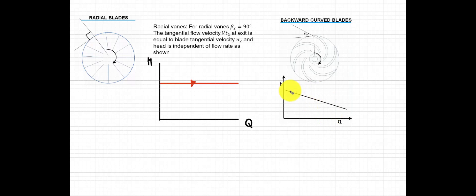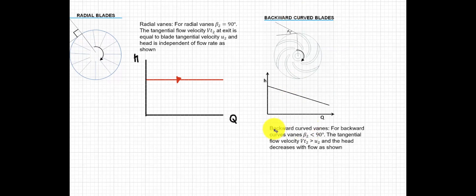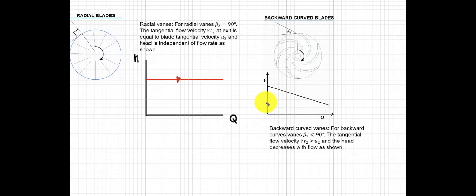It still depends on the manufacturing. Usually, you operate at the required head in the system and the corresponding volume flow rate — if you can push the fluid at that amount and that pressure required by the system. For backward curved vanes, the angle is less than 90 degrees. The tangential velocity vt2 is greater than u2, and the head decreases with the flow rate as shown.